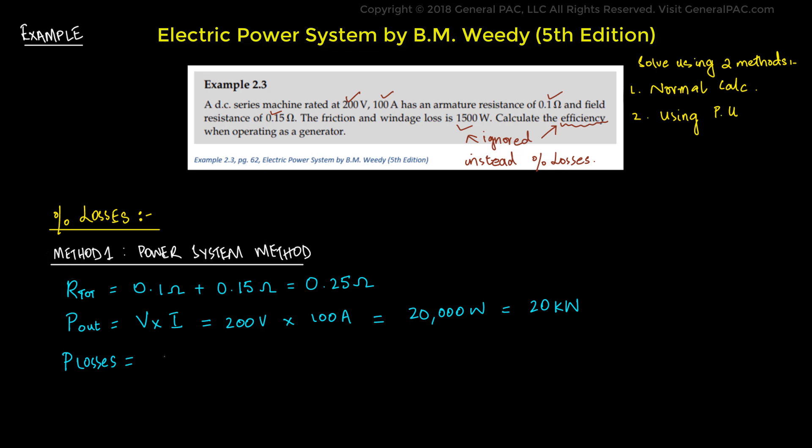The P losses is described by the equation I squared R. We get 100 amps squared times 0.25 ohms, which equals 2500 watts. The percent losses is calculated by the formula P losses over P output times 100. The P losses was 2500 watts and the P output is 20 kW or 20,000 watts. We multiply that by 100, which equals 0.125 times 100, or 12.5%. That is the percent losses.